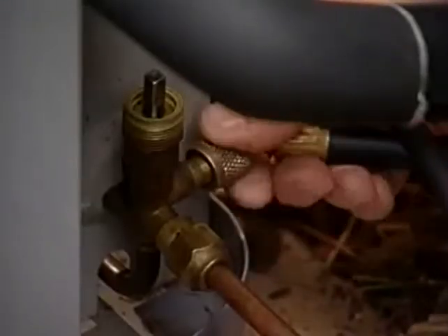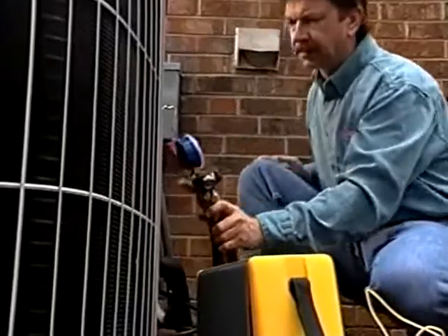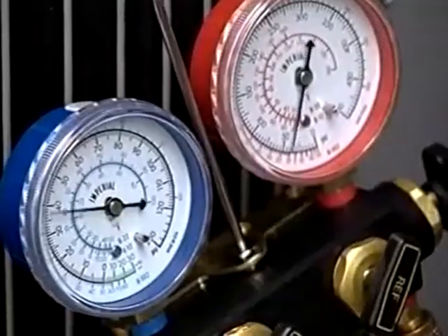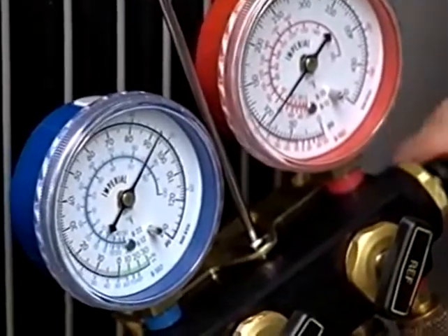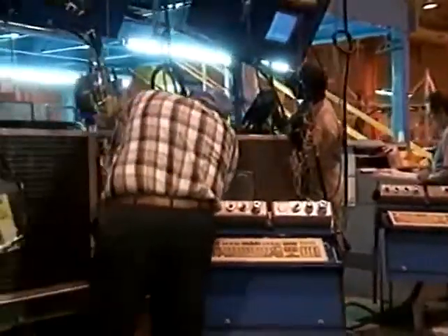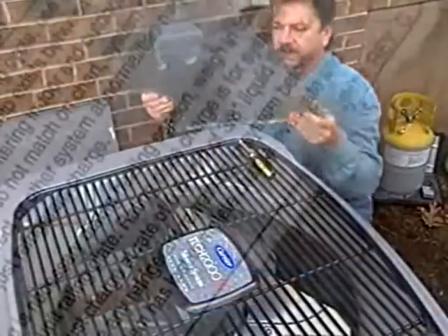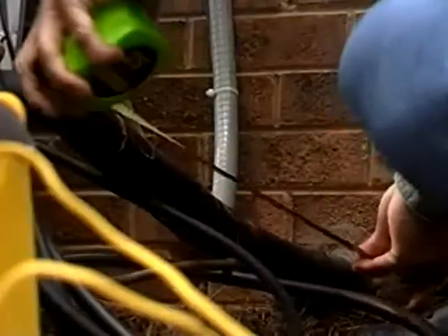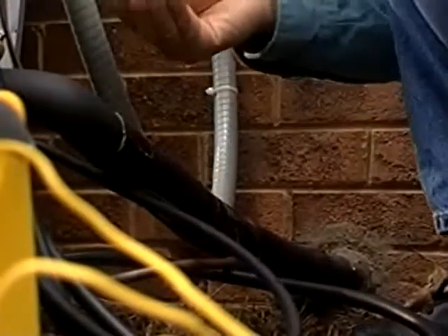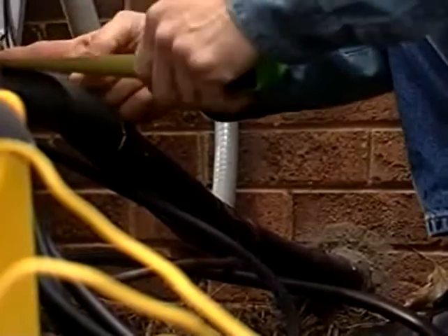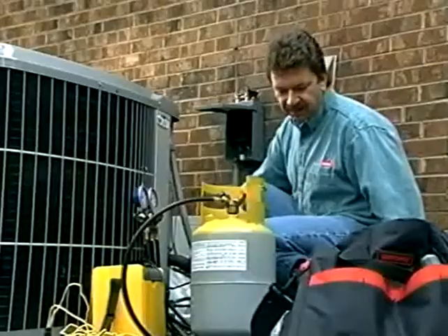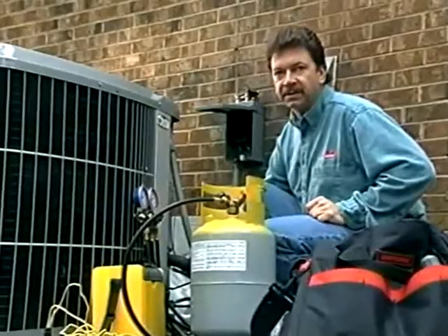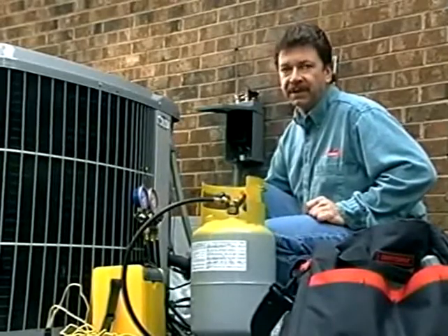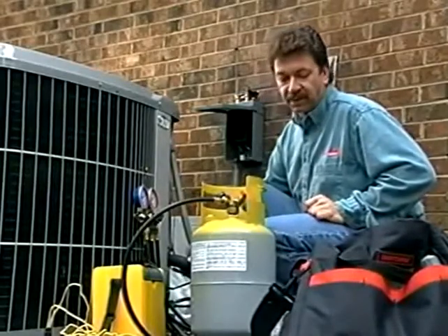The improper charging of units is another common error that causes costly comfort problems. Research shows that more than 2/3 of the units in the field are improperly charged. Condensing units come pre-charged from the factory. Most specify a specific line length. Check the manufacturer's specifications and then measure the line to see if it meets the requirements of the unit. Total line length of this unit, inside and out, comes out to be 14 feet 6 inches.